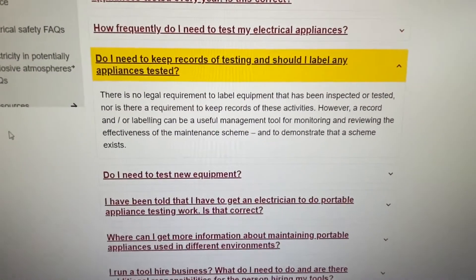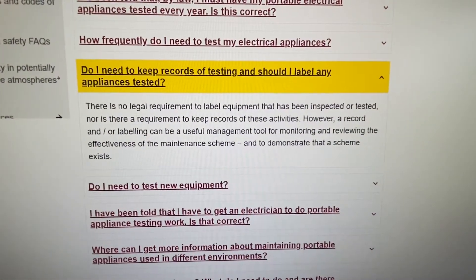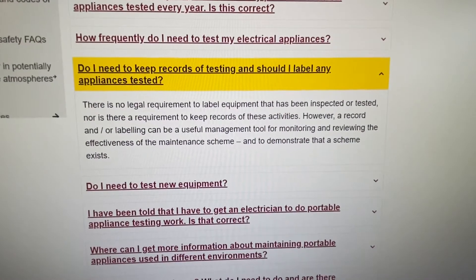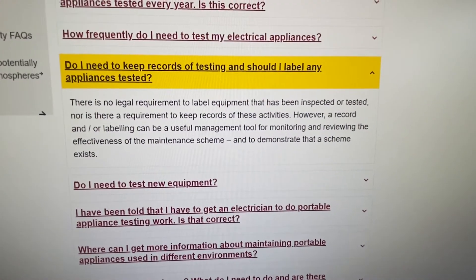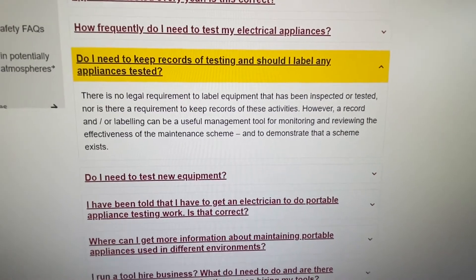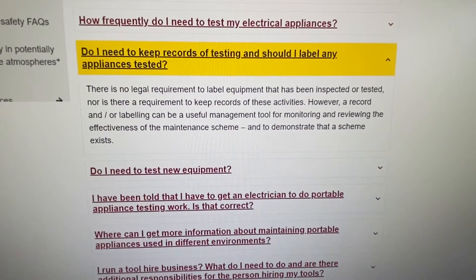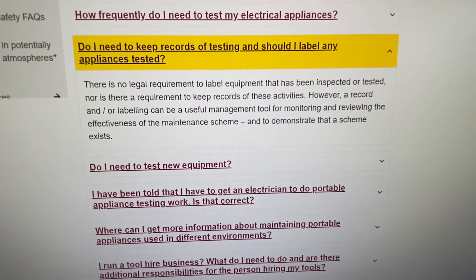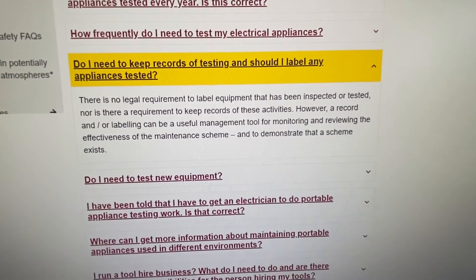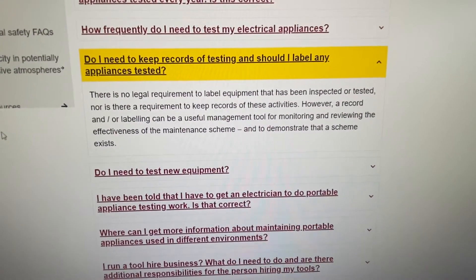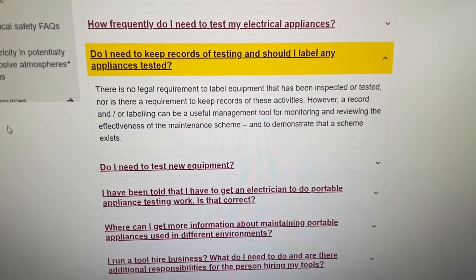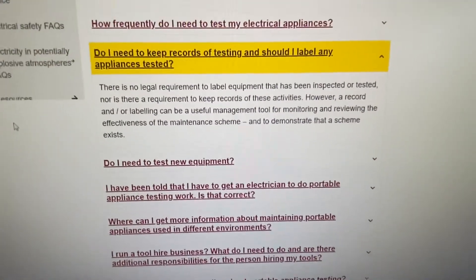So just a couple of references here. Now if you go on to the HSE website, it says here, do I need to keep records of testing and should I label my appliances? And it says there, there's no legal requirement to label equipment that has been inspected or tested and there is no requirement to keep records of these activities. However, record labelling can be a useful management tool. I think my personal opinion is stuff should be labelled and records should be kept and I think it should be a requirement.